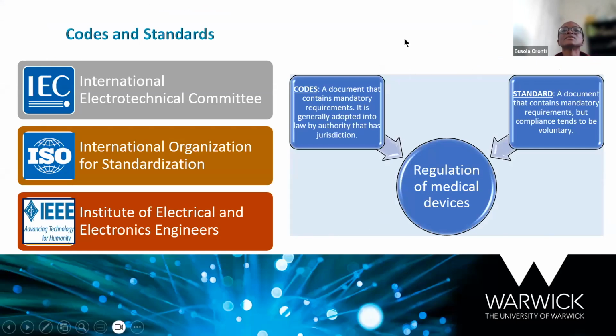Now, let's look at some codes and standards. For electrical safety of medical equipment, we have established codes and standards. Both of them are documents, but the difference is that a code is generally adopted into law by an authority that has jurisdiction, so you can be prosecuted. On the other hand, a standard is a mandatory requirement. Both of them are mandatory, but for a standard, compliance tends to be voluntary.